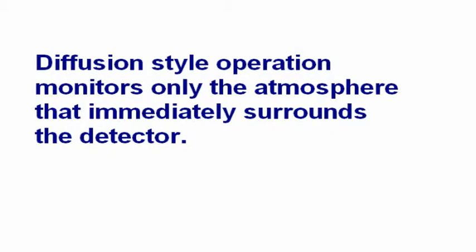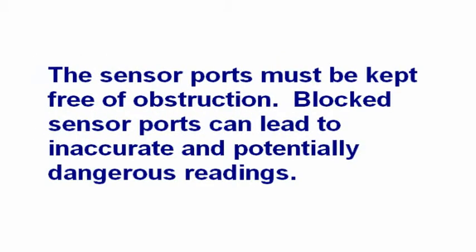Diffusion-style operation monitors only the atmosphere that immediately surrounds the detector. The sensor ports must be kept free of obstructions. Blocked sensor ports can lead to inaccurate and potentially dangerous readings.